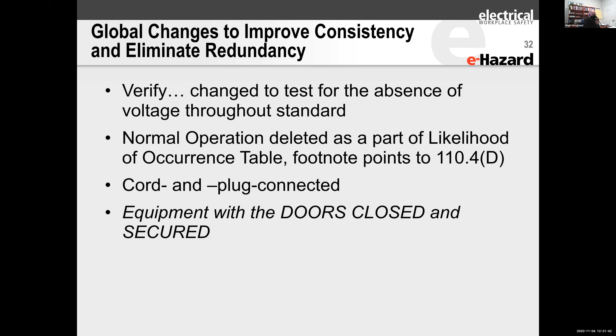We've actually seen an incident where someone closed the door back on arc-resistant equipment, but they didn't want to put all those bolts in because that was a lot of trouble. It had a lot of bolts in it. Those bolts are there for a reason. So you do have to secure them, and you should torque them correctly according to the manufacturer's recommendations. When you remove any arc-resistant equipment doors, they need to be put back exactly as the manufacturer made them because they're there to shunt the energy or contain the energy to make them safe.